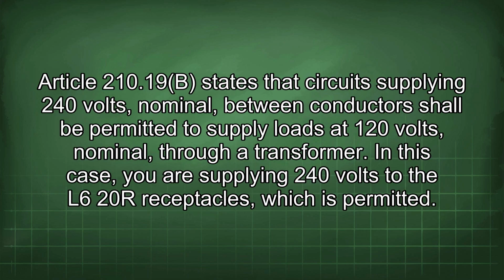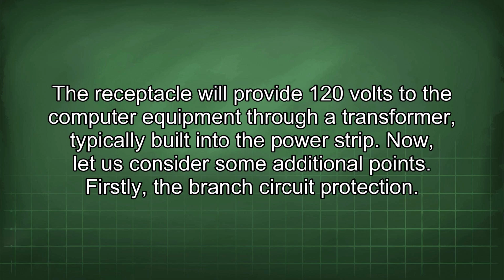Article 210.19(B) states that circuits supplying 240 volts nominal between conductors shall be permitted to supply loads at 120 volts nominal through a transformer. In this case, you are supplying 240 volts to the L620R receptacles, which is permitted. The receptacle will provide 120 volts to the computer equipment through a transformer typically built into the power strip.